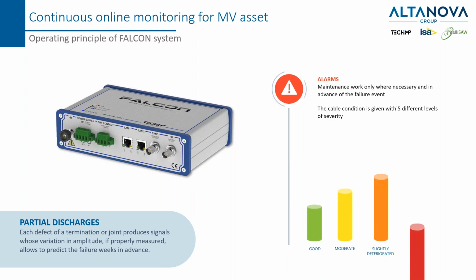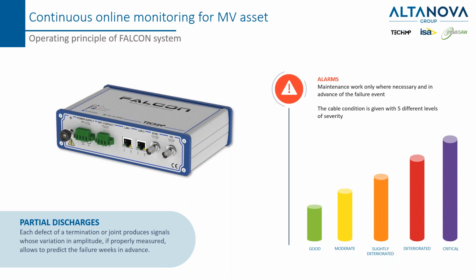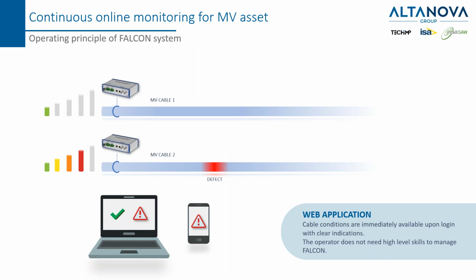Okay. Basically, one of the highlights of the Falcon unit is how user friendly it is, and in fact it can provide the alarming with different levels of severity, from good to critical. The principle is that you can have many Falcons installed in order to monitor different medium voltage cables, and in a very simple way you can connect one by one and have all in your computer or in your SCADA or whatever, and control one by one the situation of the medium voltage cable.